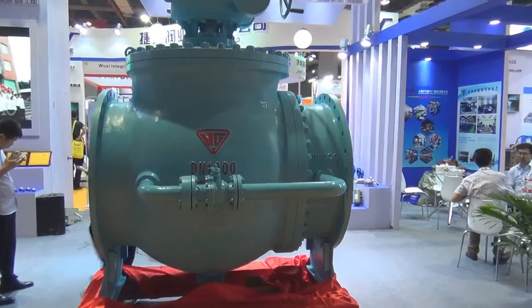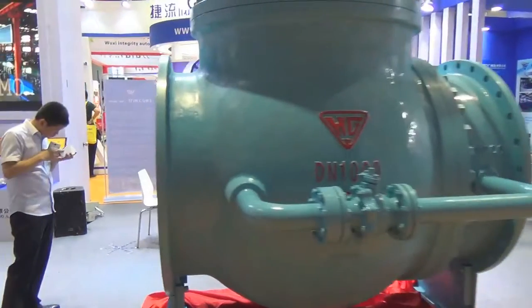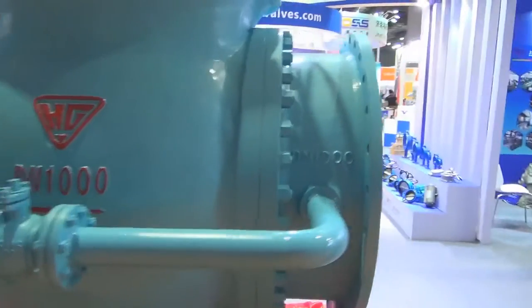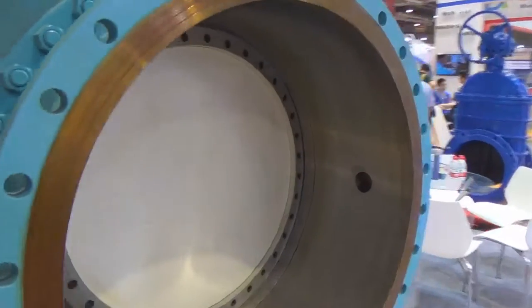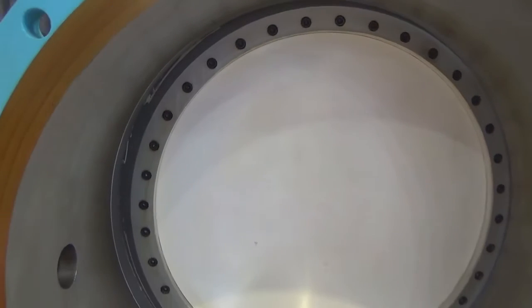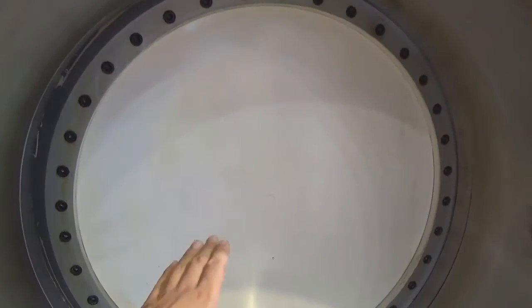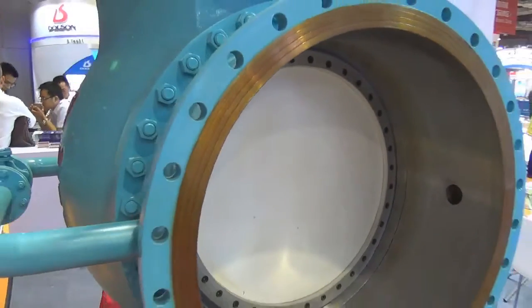Here we have a very big semi-eccentric ball valve. We use a half ball design for this kind of ball valve, and also the valve stem is not in the center of the valve body. So we call this kind of ball valve a semi-eccentric ball valve. When the valve is going to open, the ball sealing face will immediately leave the valve body seat sealing face. So the ball will not grab the valve seat. So when we open this kind of ball valve, it has no rubbing. The white color is just paint, not another kind of material.